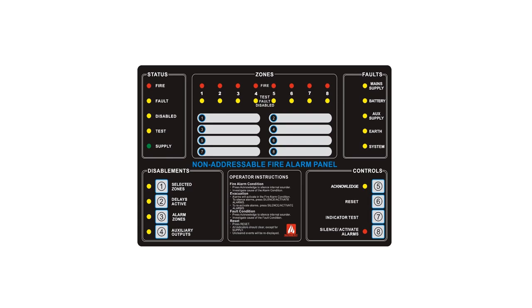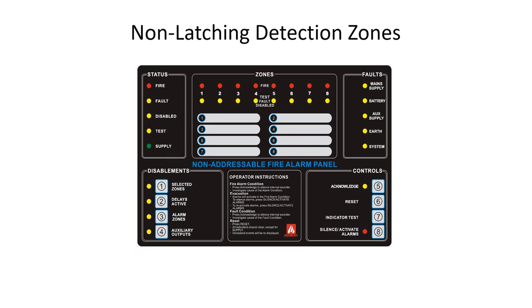Detection zones can be configured to be non-latching. Non-latching detection zones only enter the alarm condition when a fire phenomena is present, automatically returning to the quiescent condition when the fire phenomena dissipates. When configured for non-latching operation, incoming fire signals will activate alarm zones but will not activate the fire alarm relays. At the same time, faults are also non-latching, so the fault relay will not activate.